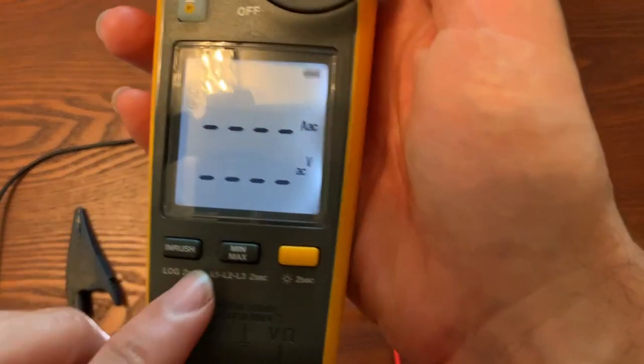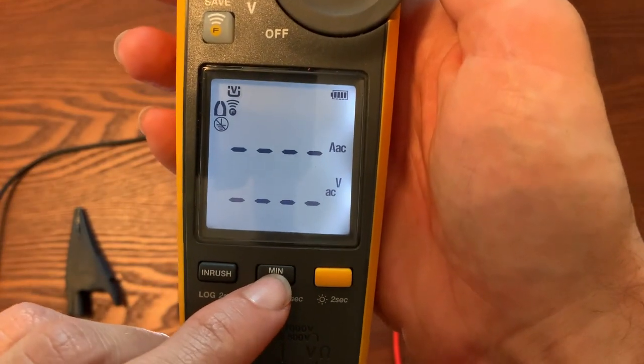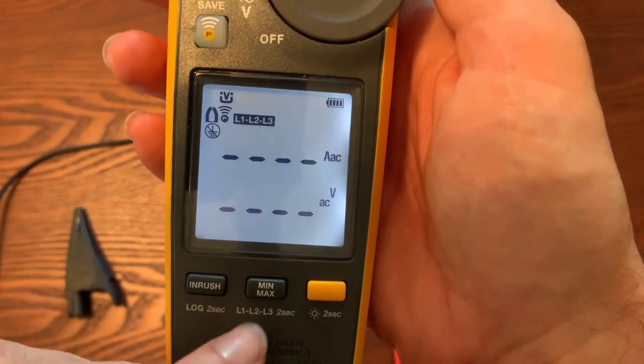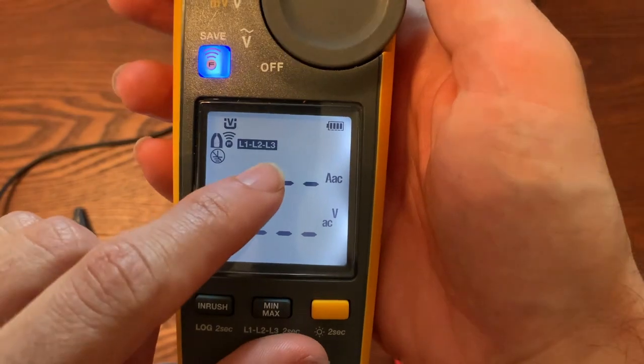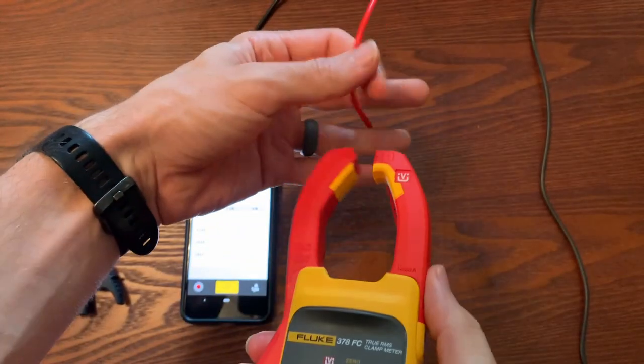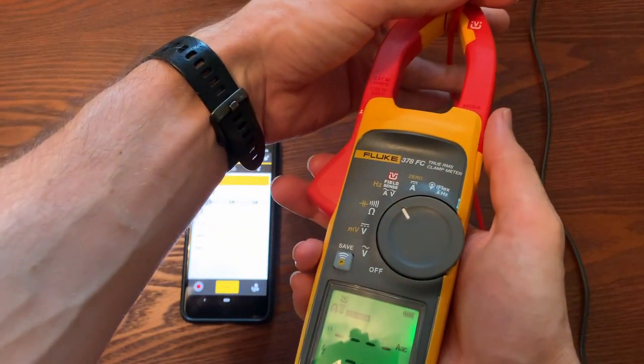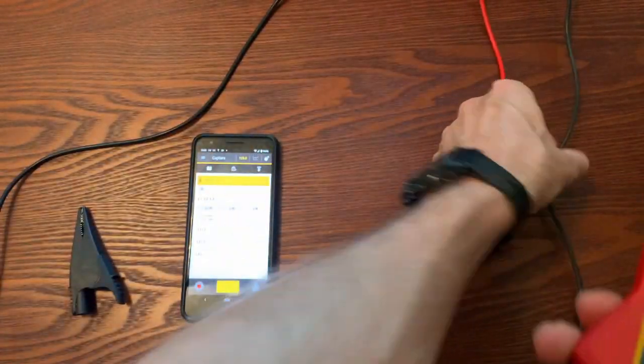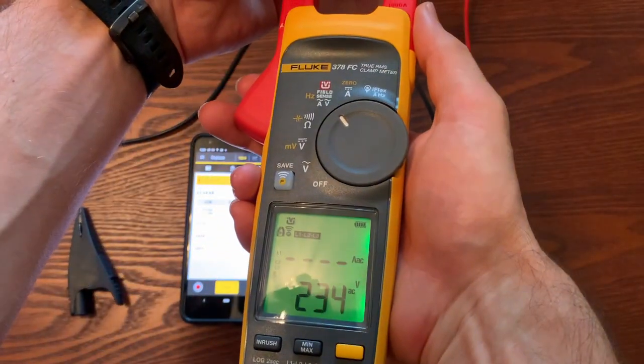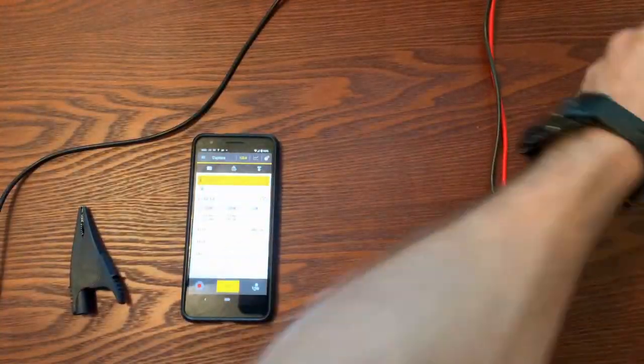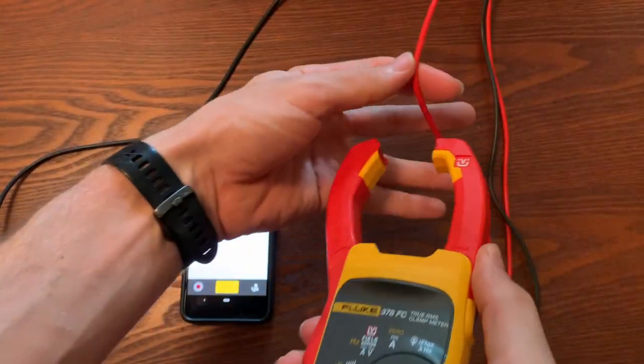What I'm going to do is a three-phase measurement. I have to hold that middle button down, that min max button down, till it turns on the L1 L2 L3. You clamp around, the screen is going to turn green, you're going to hear a beep, and then you're going to move to the next leg as you go through.